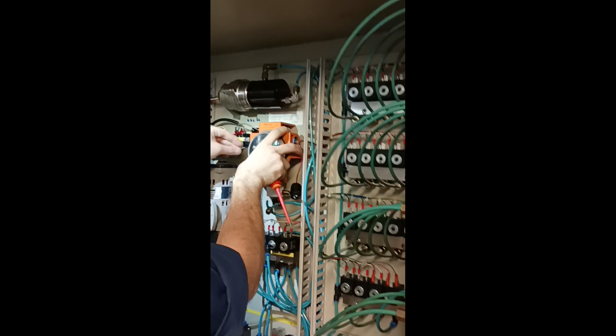The regulation is this should be replaced once every 2 years for the toxic gas sensor or the H2S sensor, while the LEL sensor is every 5 years. The sensor is quite expensive.